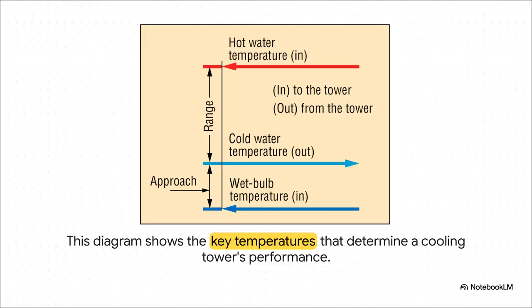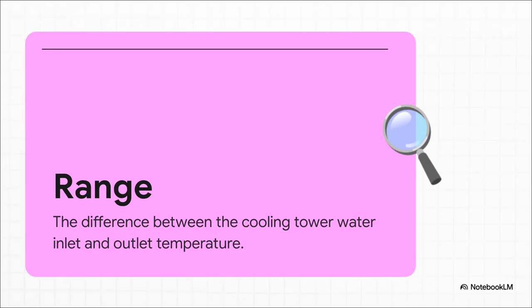This visual right here tells you pretty much everything you need to know. Performance is all about the relationship between a few key temperatures. You've got the hot water going in, the cold water coming out, and something called the wet bulb temperature of the air. This gives us our 2 critical metrics, range and approach. First up, we have range.